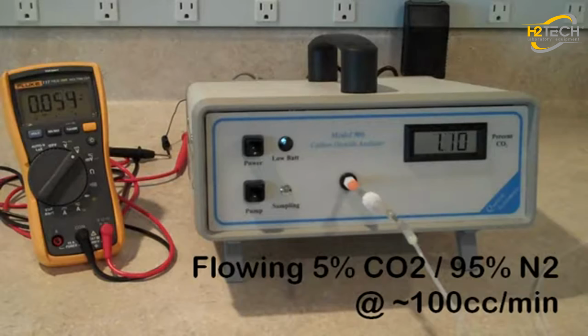We're going to start by flowing 5% CO2 through the analyzer at a flow rate of about 100 cc's per minute. We recommend flowing your gas at a rate of 10 to 1000 cc's per minute.